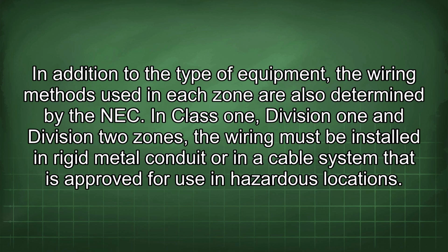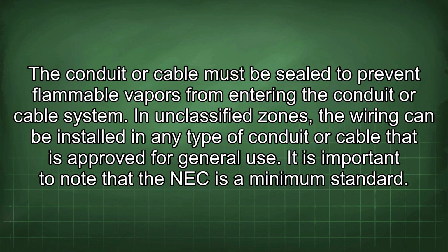In addition to the type of equipment, the wiring methods used in each zone are also determined by the NEC. In Class 1, Division 1 and Division 2 zones, the wiring must be installed in rigid metal conduit or in a cable system that is approved for use in hazardous locations. The conduit or cable must be sealed to prevent flammable vapors from entering the conduit or cable system. In unclassified zones, the wiring can be installed in any type of conduit or cable that is approved for general use.